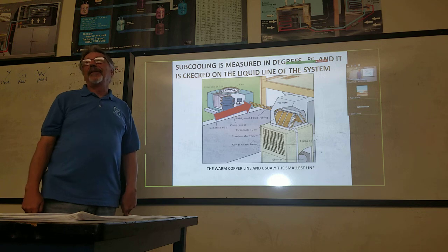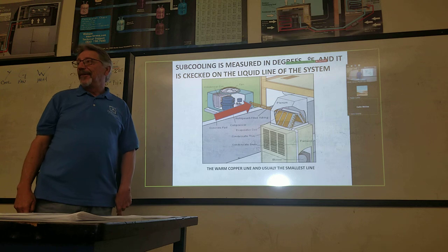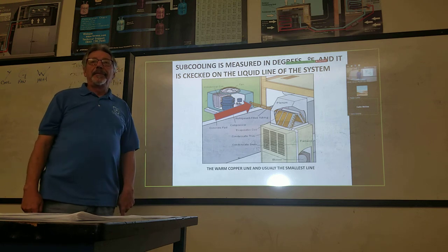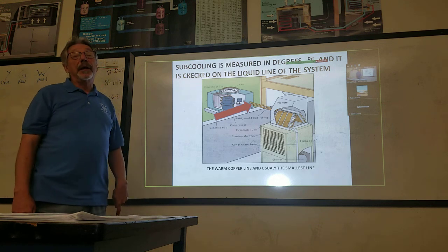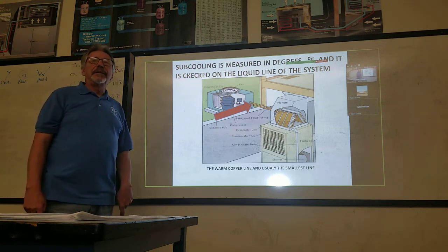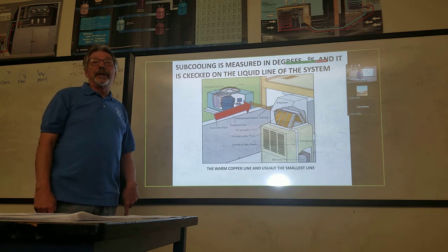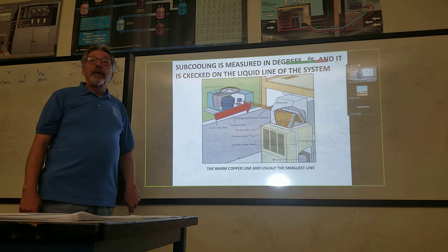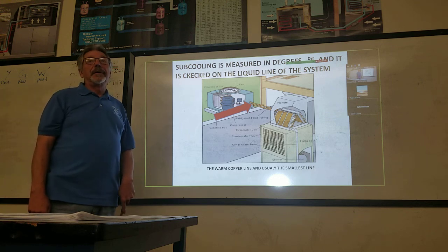I know, somebody going, oh, come on, really? Steve, which one gets the insulation? The cold one. So the liquid line is usually the bigger, colder one? No, not the liquid line. Superheat's cold. The big one is the suction line. You said the liquid line. The liquid line is the warmer one. So it's the opposite. Subcooling's cold? Big one cold, little one warmer.